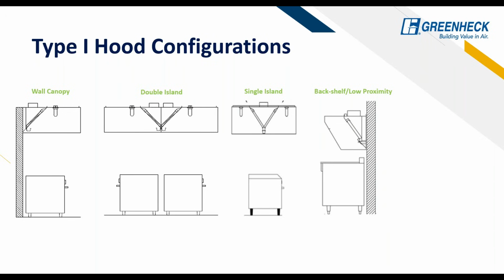Different types of hood configurations here. The most standard is that wall canopy hood on the left there. Then you have a double island hood configuration. Most of the time with those double island hoods, they're actually just 2 wall canopies back to back, and that can serve a double island situation. Or you have the single island hood, which does require a lot more CFM than a wall canopy hood, and that's 12 inches of overhang as well.